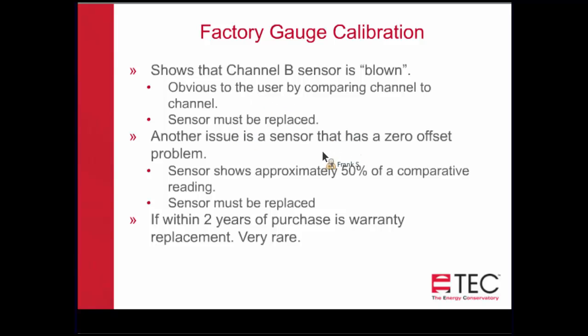There is another issue that can affect sensors that has to do with the zero offset problem. This is one of those cases where you might be able to compare one sensor on channel A to channel B, and if you see that they are roughly 50% off from each other, and it's usually 50% low, it's rarely 50% high. So if you see one that's reading 100 and another one that's reading 50, chances are the sensor that's reading 50 has this zero offset problem, and that also needs to be replaced. And if you have it within 2 years of purchase, then we will certainly replace that under warranty.